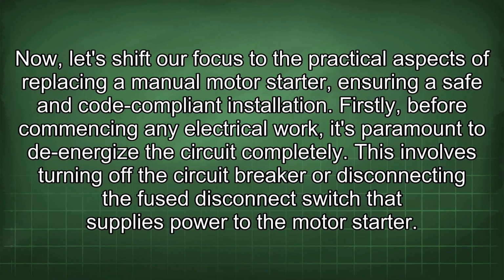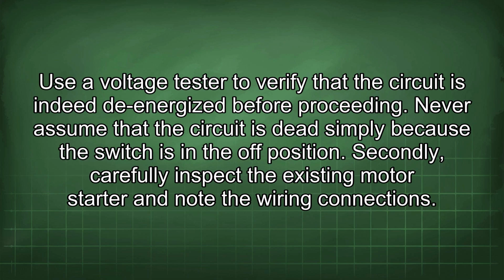Now let's shift our focus to the practical aspects of replacing a manual motor starter, ensuring a safe and code-compliant installation. Firstly, before commencing any electrical work, it's paramount to de-energize the circuit completely. This involves turning off the circuit breaker or disconnecting the fused disconnect switch that supplies power to the motor starter. Use a voltage tester to verify that the circuit is indeed de-energized before proceeding. Never assume that the circuit is dead simply because the switch is in the off position.